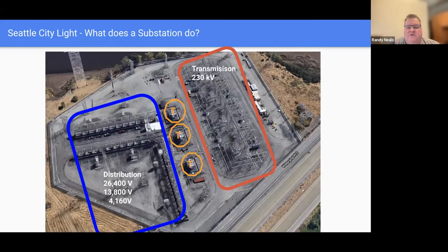Back to that picture of the Duwamish station. On one side is the transmission side, where the 230,000 volt lines from BPA and the rest of the network come in. There are transformers in the middle, the same big things shown being moved in on a truck. They sit between the 230,000 volt side and the distribution side, where Seattle's distribution voltages run around 26,000, 13,000, or 4,000 volts depending on the area. These are the voltages on the wires atop poles around our city, adapted by pole-mounted or underground transformers into voltages we can actually consume.